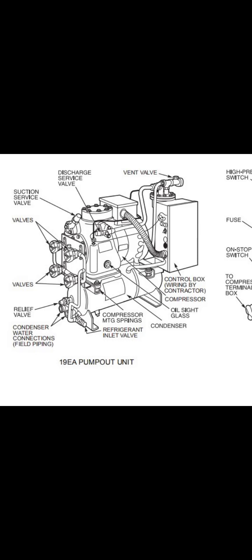So what happens is the hot gas pushes in the evaporator, and the condenser, where refrigerant is being taken out, gets low pressure. With the pressure difference, the liquid is pressed and transferred into the condenser. When you think all the liquid refrigerant has transferred into the condenser, you close the liquid line valve. Now both are isolated. Also close the condenser upper valve, and both downward isolation valves. So the condenser is separate and the cooler is separate.